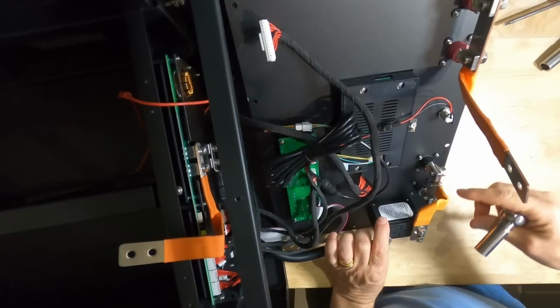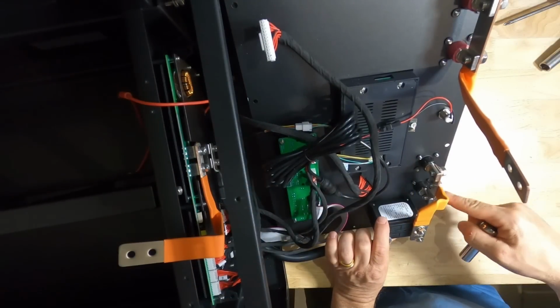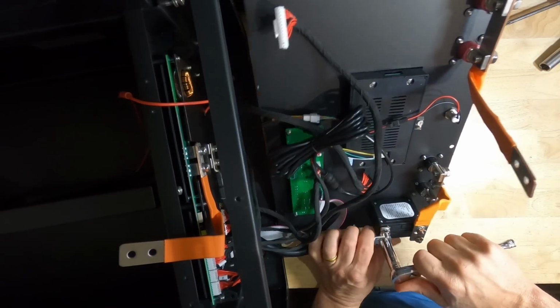The M6 and M8 bolts on the breaker and the battery terminals inside the battery were pretty much all loose. The reason they gave me was that the customer might want to take it apart, but it comes pre-assembled. I told them there's no reason to take it apart, so just tighten them up at the factory and let it be like that. Definitely check those bolts, and hopefully they fix that in the future.